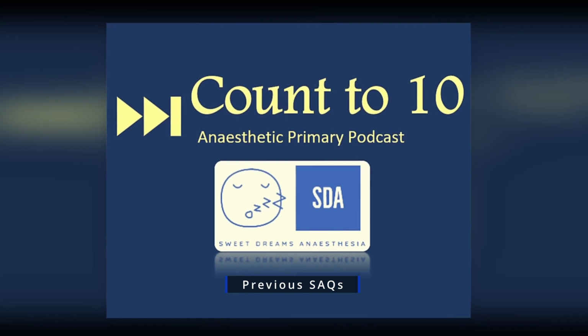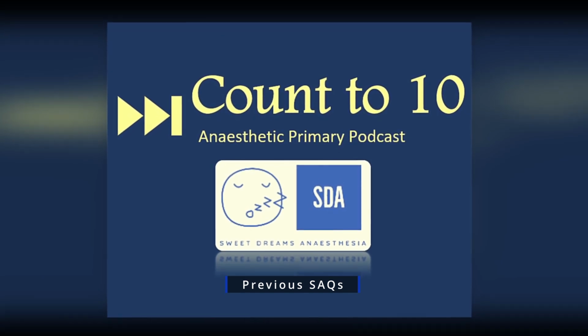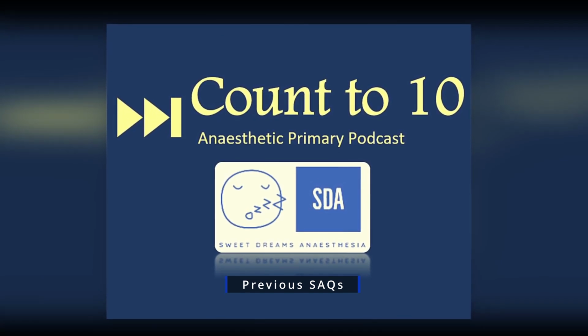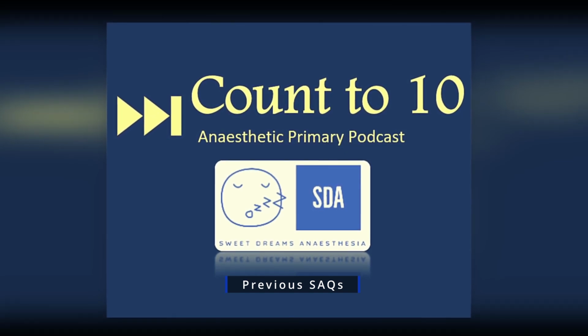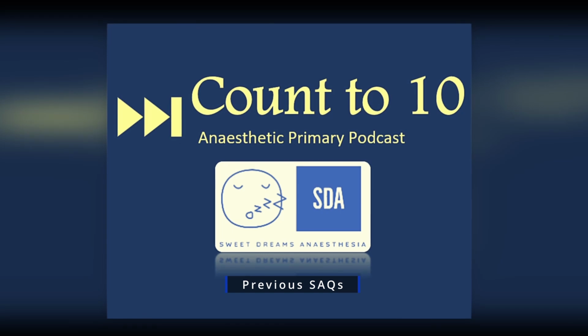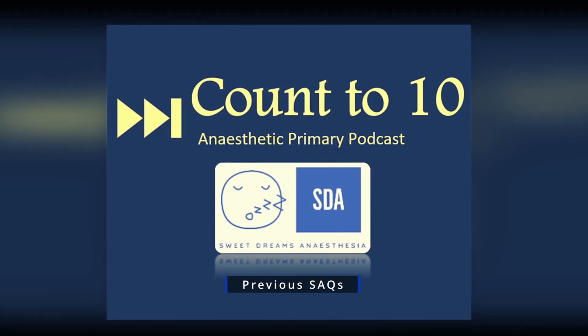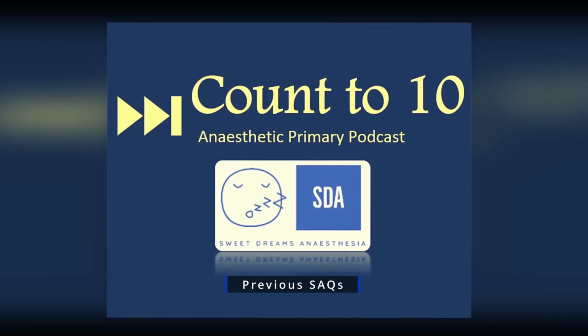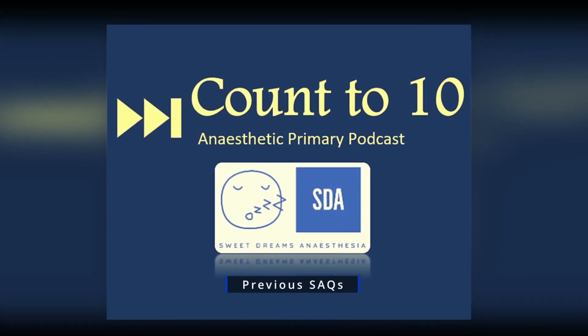Using the proprietary algorithms, there are then different types of analysis that are done on those small epoch data sets. The first type of analysis is a time-based analysis, and this looks at the burst suppression ratio. So this is the percentage over a 63-second period in which a burst suppression pattern is seen.